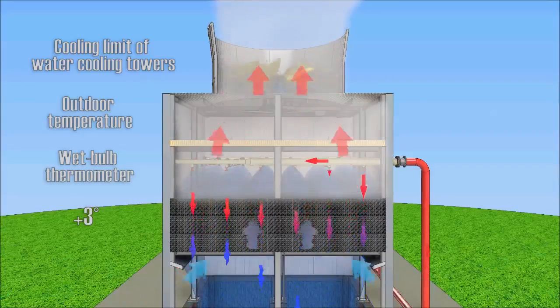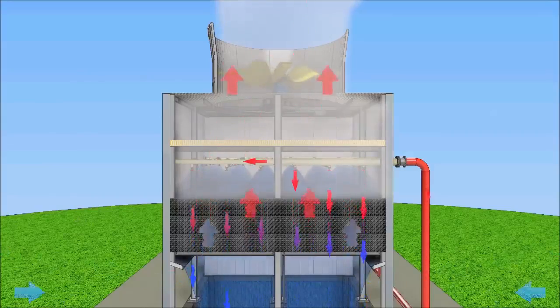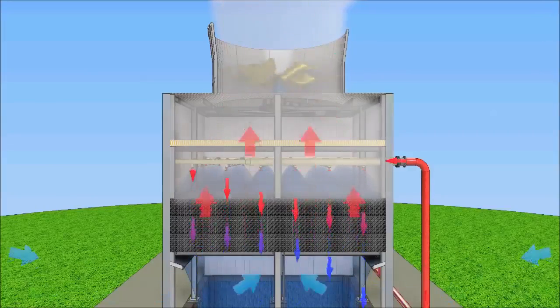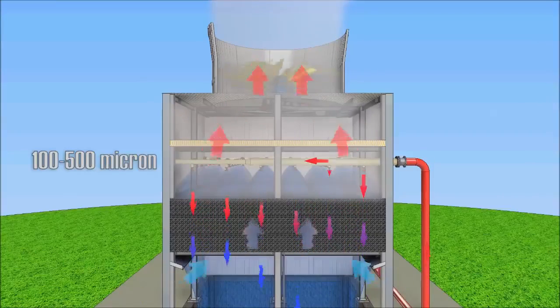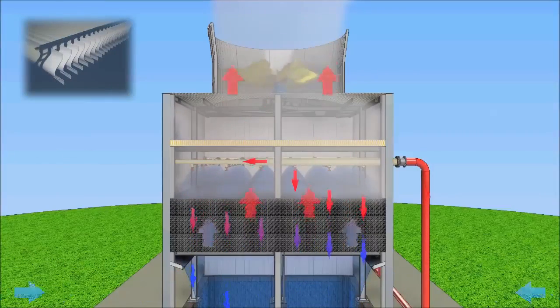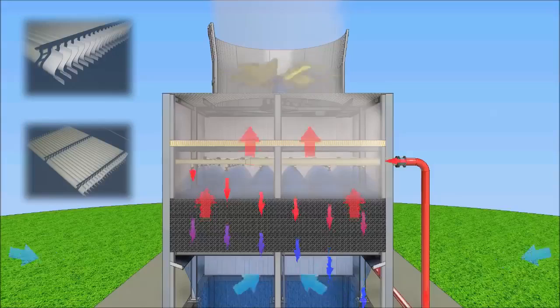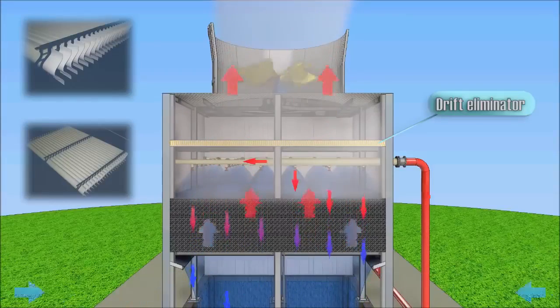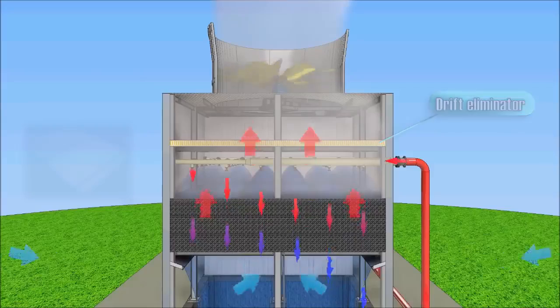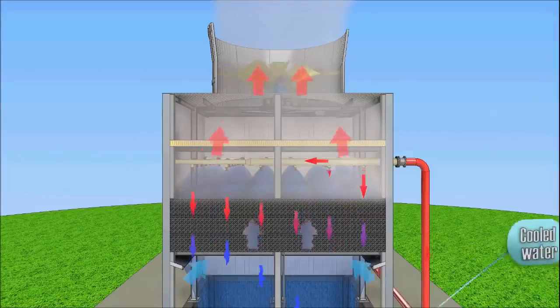In practice, the limit of cooling is the temperature of the wet bulb thermometer plus 3 degrees Celsius. Operating a cooling tower emits air saturated with water vapor and containing water droplets with size of 100 to 500 microns. To prevent entrainment of water droplets, above the water distribution system is installed a drift eliminator.